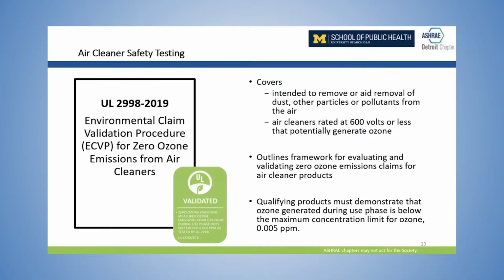And even if that performance test data is a little fluid, the safety testing should not be. Any equipment you bring into a school building should have appropriate safety certifications. For example, some air cleaners have a known potential of creating ozone as a byproduct. We know that ozone is a pollutant, and so in that case, if we were bringing in in-room air cleaners, we would want to make sure that they have been tested and that they have a UL sticker for UL2998 certifying that they produce ozone below the threshold level of 0.005 parts per million.